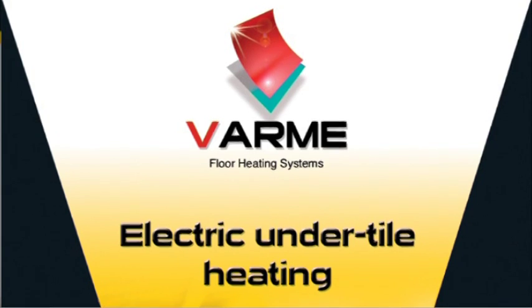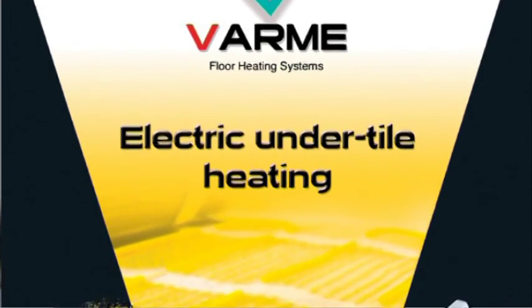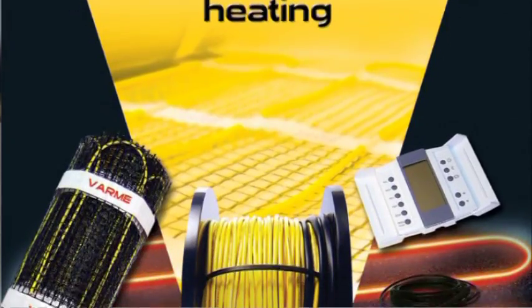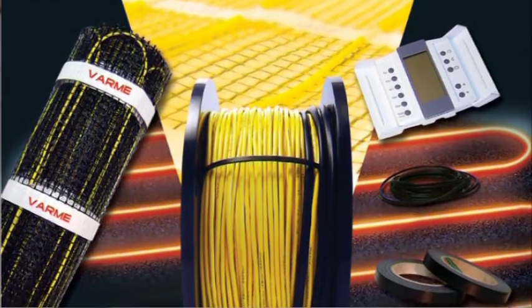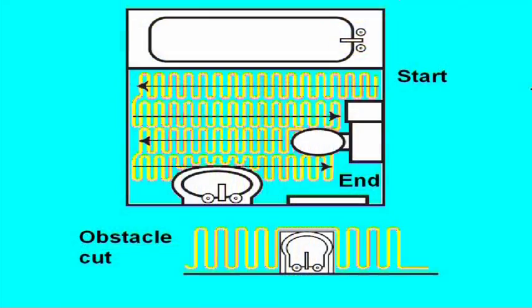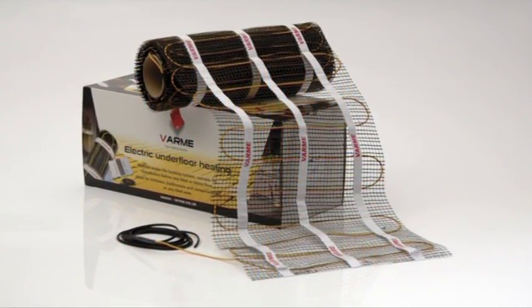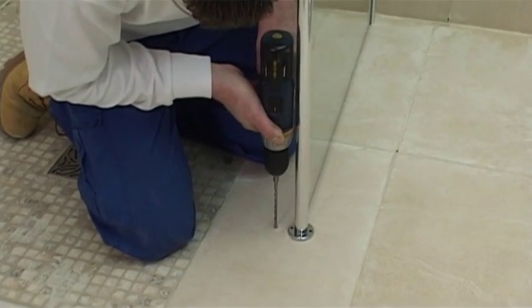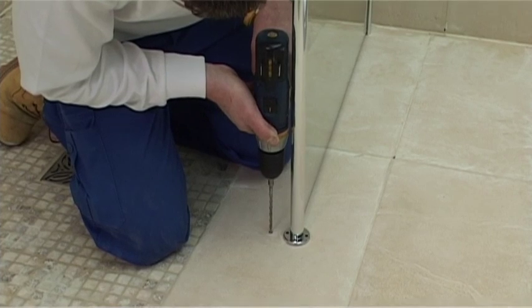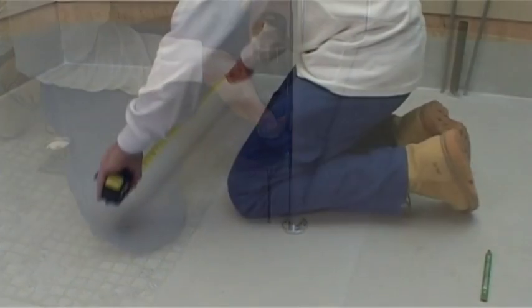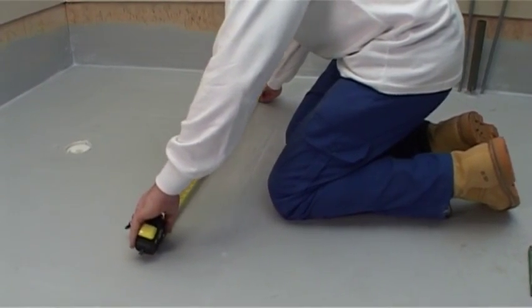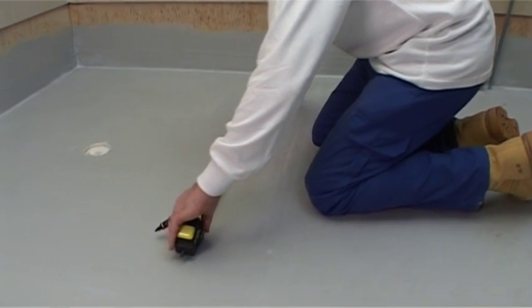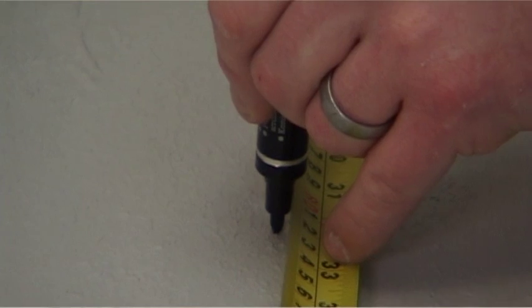You must size the heating mat to fit the floor area and make any additional preparations recommended by Varme for your particular floor conditions. The mat must not run under any bathroom furniture such as baths, bidets or WCs. The yellow cable on the mat must run clear of all shower screen fixings. Ensure the shower screen installers know the importance of getting the screen position agreed in advance, and that this position must remain unchanged once the mat is in place.